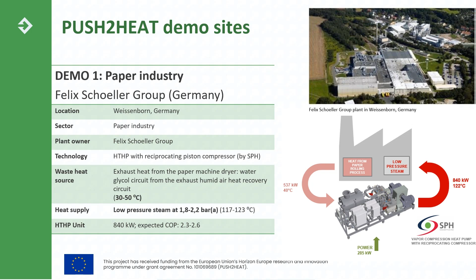Here we are talking about quite an important temperature lift, probably not as high as one of the demo sites explained by Andrew that is part of Spirit, but here we are talking also about a temperature lift of 80 Kelvin more or less. This translates into the COP as well, and it's expected to have quite an interesting COP. We are still in the initial stages of the project, doing the first assessment, the energy system concept and so on, so accurate results will come later, but we expect a COP around 2.3 to 2.6. Regarding size, we are talking about a high temperature heat pump unit of about 840 kilowatts of delivered heat.